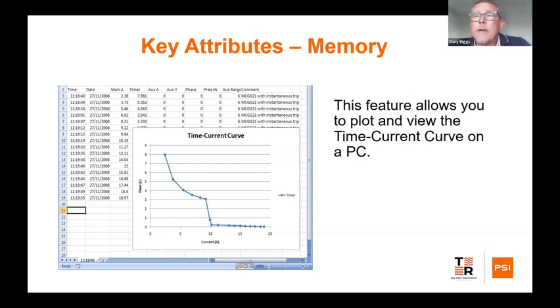Now, many of the manufacturers of the relays themselves will offer you the ability to download their time current curve graph. And that allows you then to overlay your results onto their graph and be very confident whether the relay is indeed in spec or whether there's a part of that relay that's out of spec. And it's very quick and easy to do that.